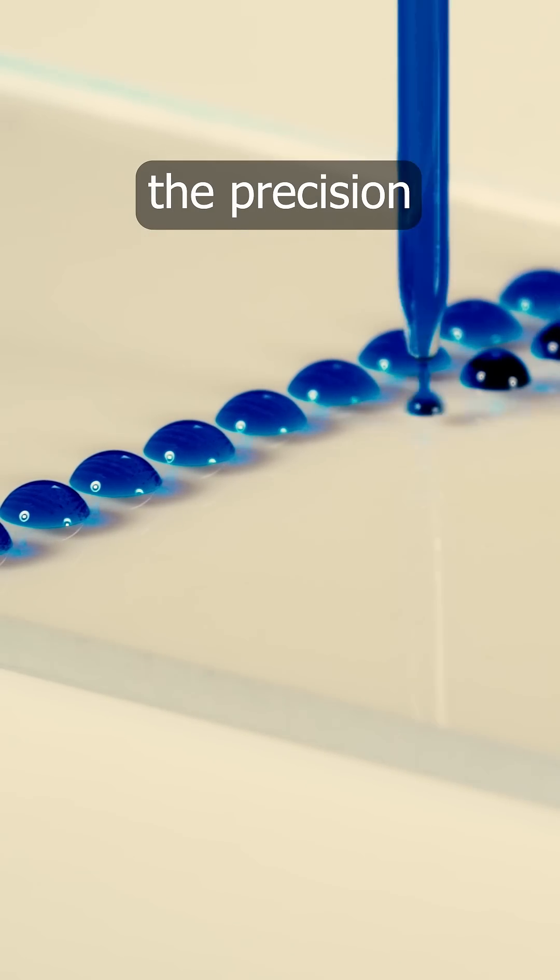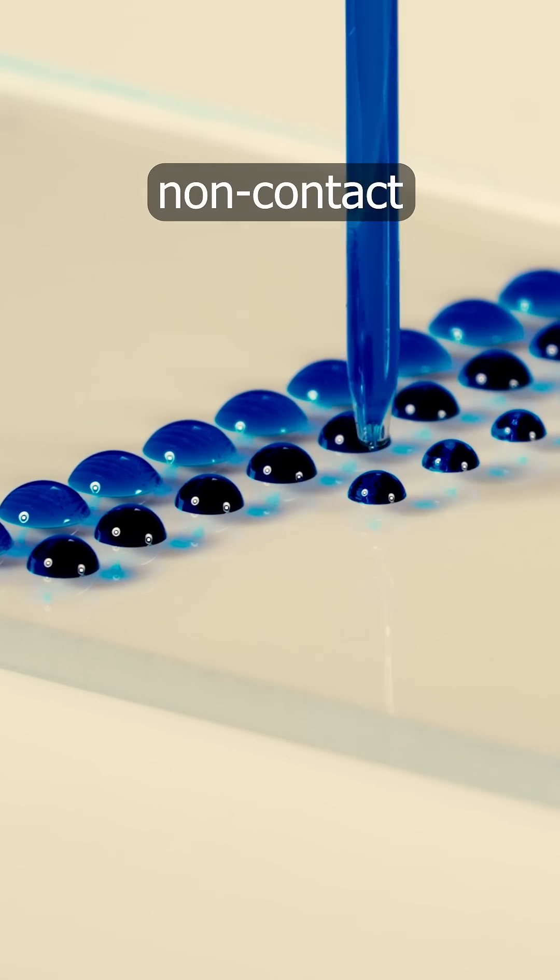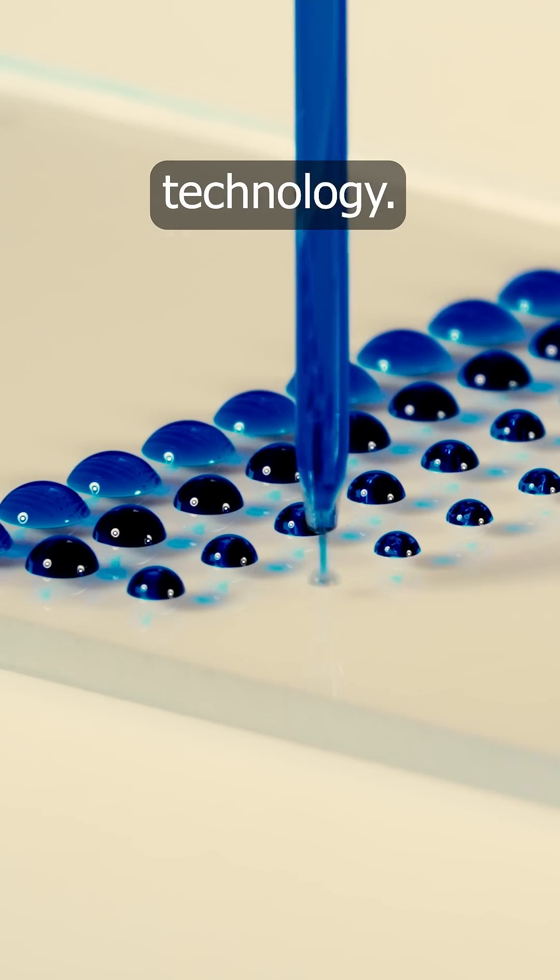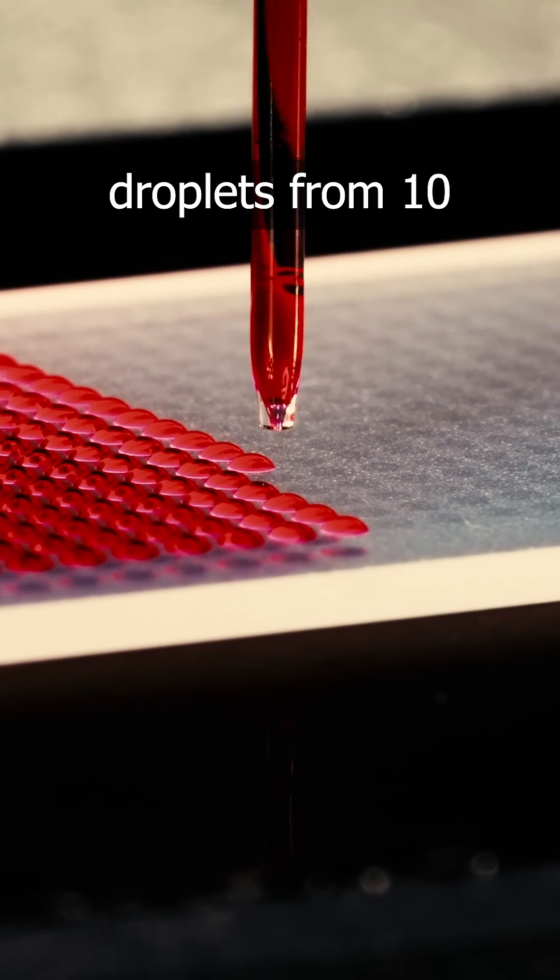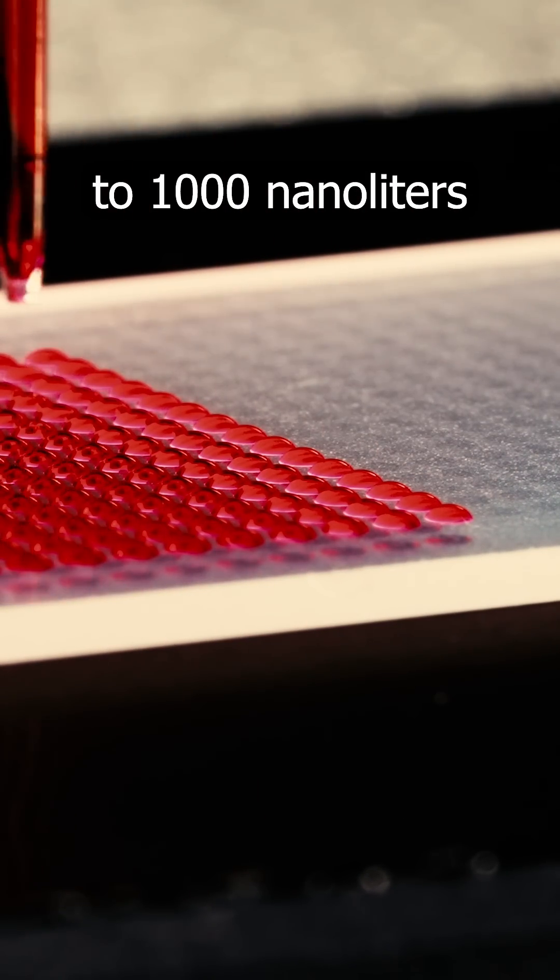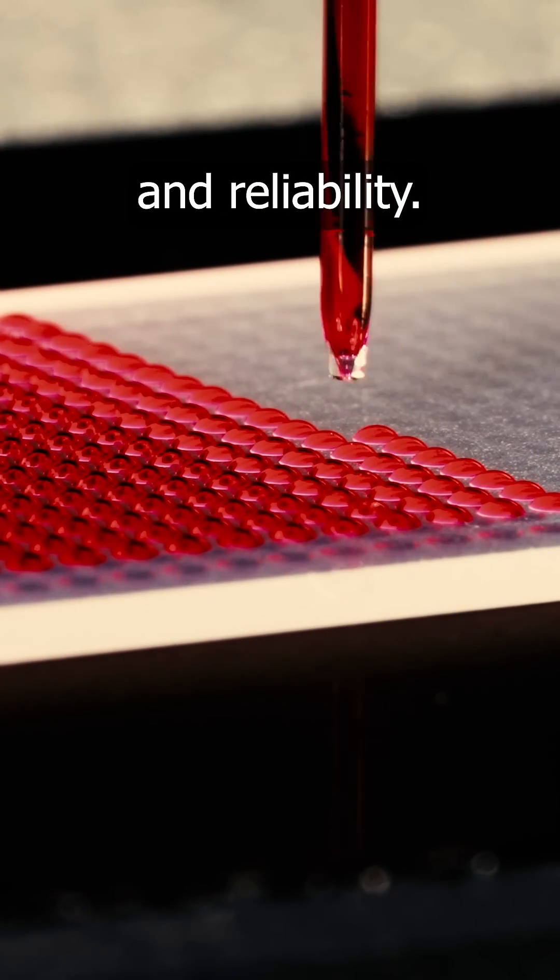Experience the precision of M2 Automation's non-contact nanoliter dispensing technology. The M2MD delivers droplets from 10 to 1,000 nanoliters with outstanding accuracy and reliability.